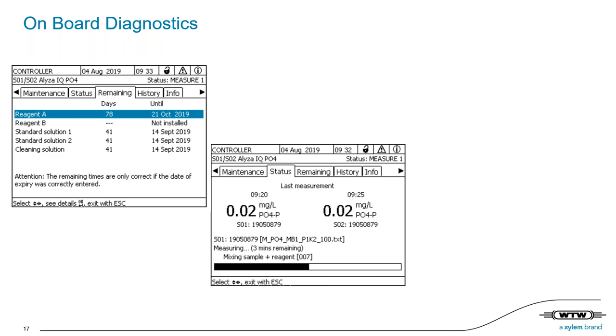I got questions in the past when to use the automatic 2 point calibration, what is new and unique for that analyzer. So if you're measuring at very low concentrations and you need a high accuracy, I would recommend to have an automatic 2 point calibration, but also once per day is suitable.